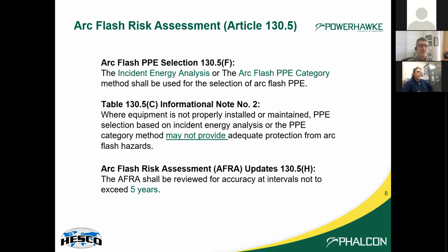130.5F says that you can use either an incident energy analysis, otherwise known as an arc flash risk assessment, or the arc flash PPE category method. In NFPA 70E, there is a set of tables that allow you to go through a decision tree and determine the PPE using that method in lieu of the incident energy analysis. The preferred path is still the arc flash risk assessment, but there are these two methods.